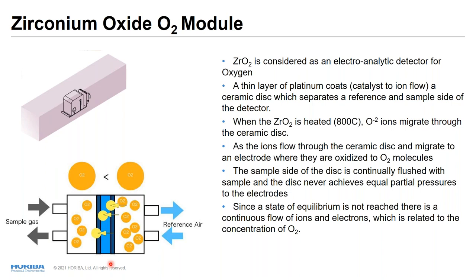So you have two chambers here, right? The sample gas chamber and the reference gas chamber right there. They are divided by a ceramic disc, and one chamber is continuously fed by a sample gas, and the other chamber is continuously fed by the reference air. And oxygen migrates from higher concentration to lower concentration.